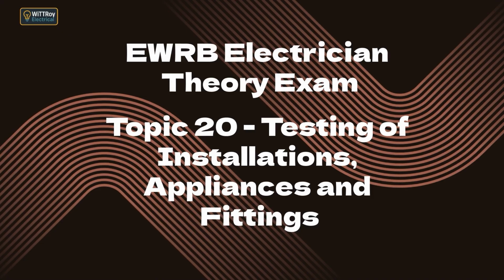Topic 20K. Explain that following repairs, electrical appliances must be tested to ensure they are safe in accordance with the requirements of AS/NZS 5762, Regulation 92. After repairing an appliance, it must be retested according to AS/NZS 5762. Regulation 92 requires that the appliance is proven electrically safe before returning it to service. This includes an insulation test, earth continuity, polarity, and an operational test.